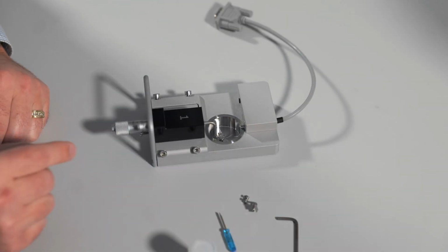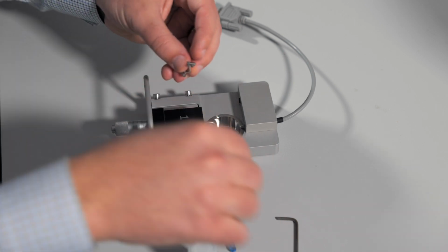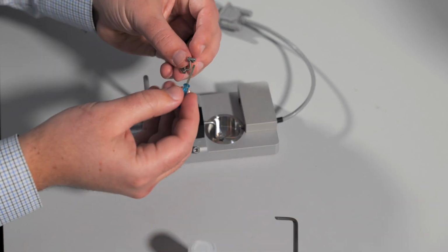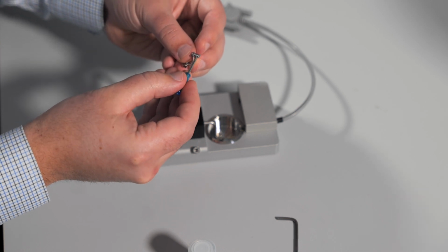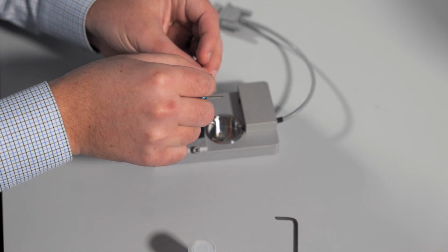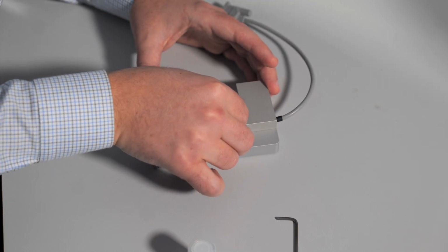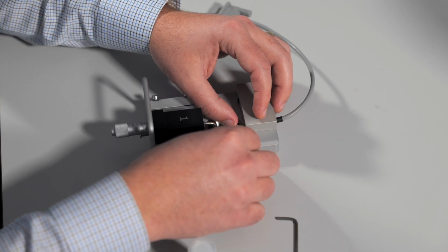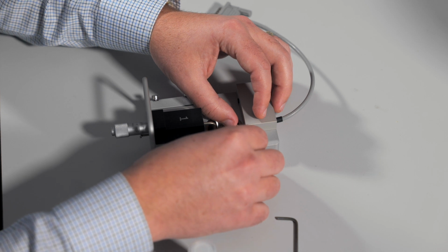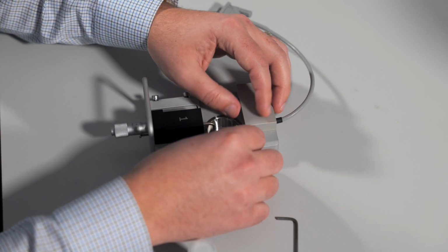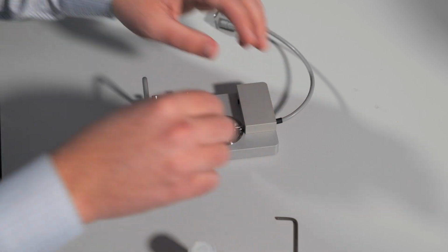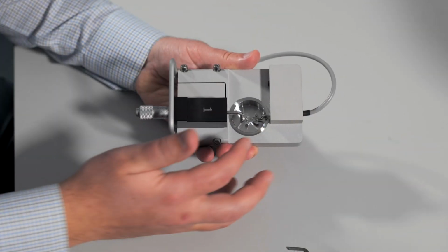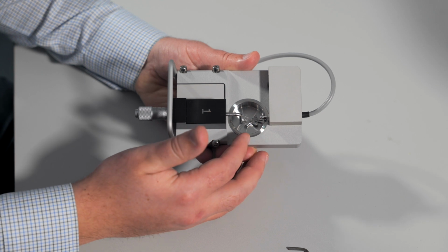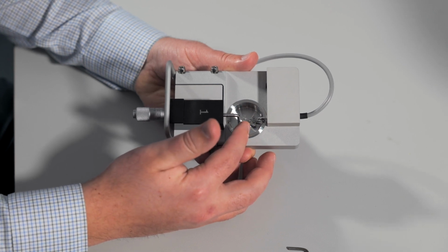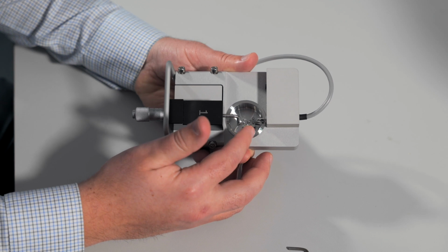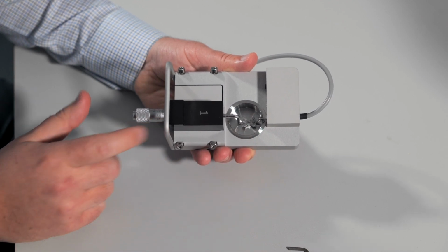You should now replace the tissue mount on the transducer side. You will need your screwdriver and the mount. Make sure that the back screw is loose and add it in place. You just want to make sure that the mount is flat and level in the chamber. Tighten the screw securely, but do not over tighten as you could damage the transducer. After replacing the transducer and the tissue mount, you will need to make sure that your mounts are aligned under the microscope, perform a force calibration, and then the chamber is ready for experiments.